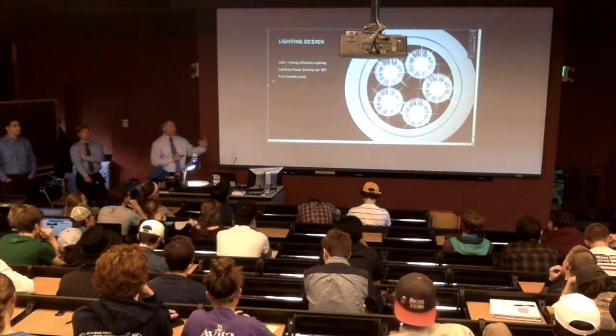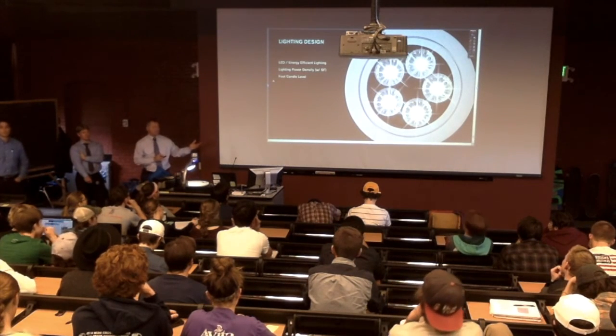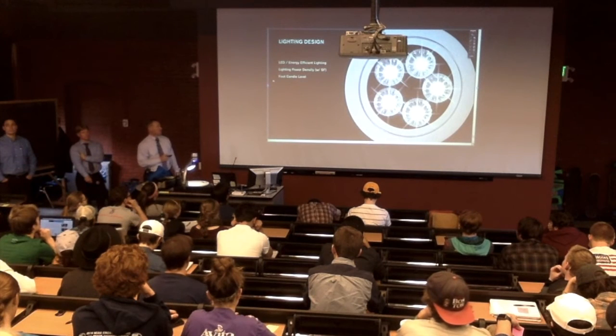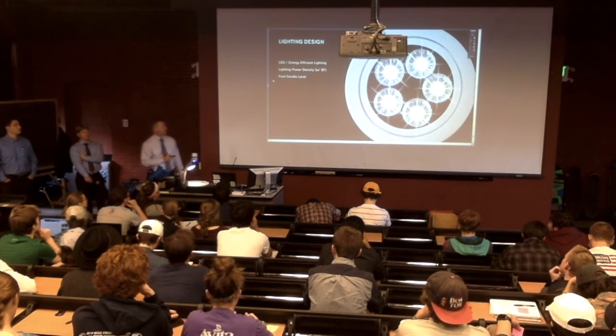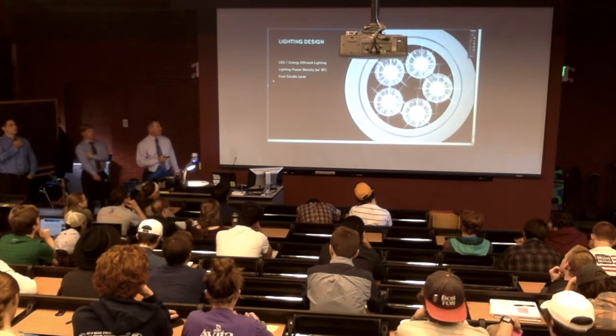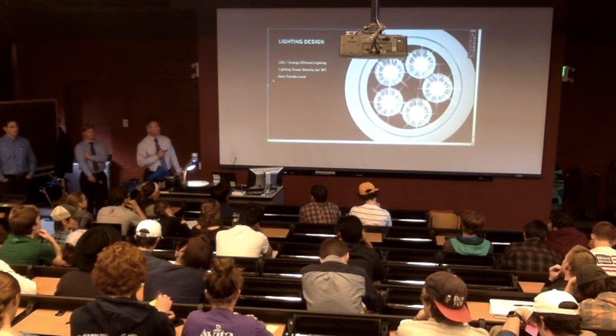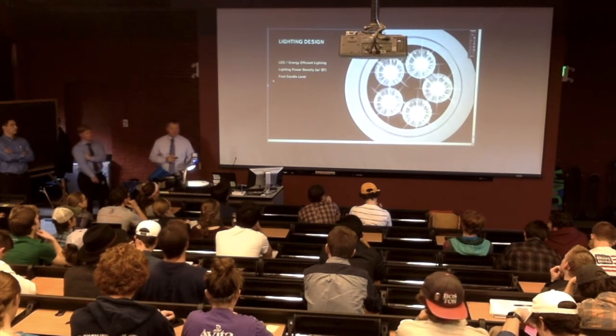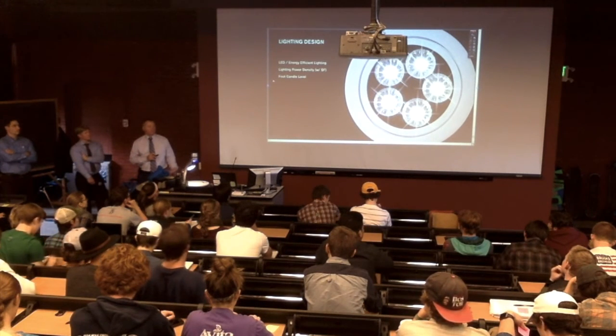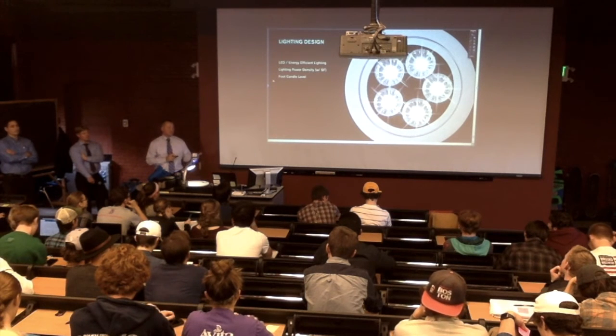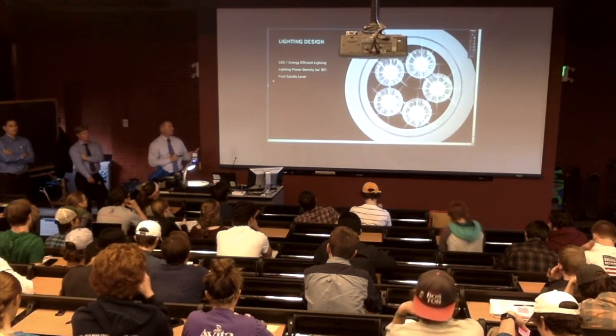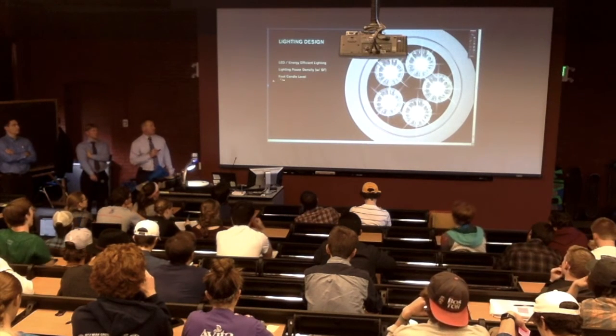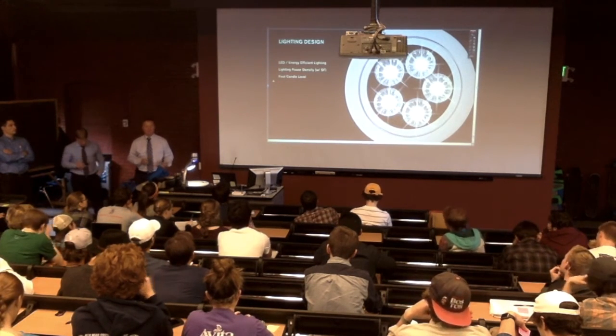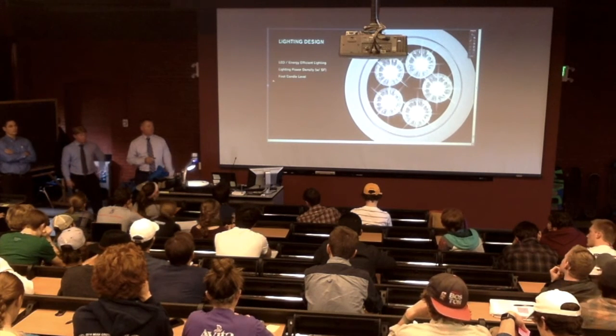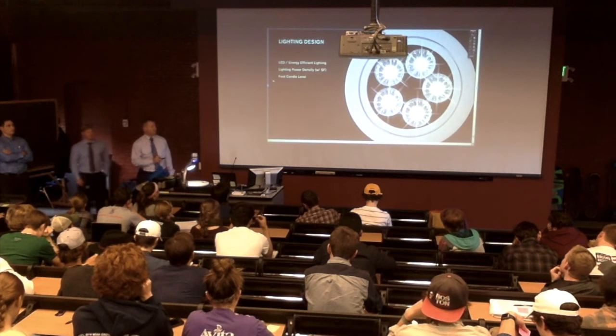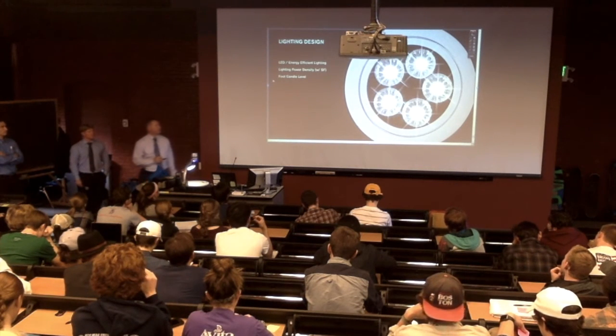And then, as I mentioned earlier, from a building standpoint, lighting is a very important component. Not only natural light, but artificial light. Artificial light, generally we're using LED fixtures. They're substantially more efficient than fluorescent fixtures or compact fluorescent. So we're trying to make sure that you know this term, LPD, or lighting power density. We used to design for 1.5 watts a square foot. We're down to 0.5 to 0.75. So the amount of energy consumed in lighting in the building has dropped more than half. But we still have to maintain a foot candle level so that when you're writing on a desktop, you can actually see what you're writing on. So all those components go into the electrical design side of the project.